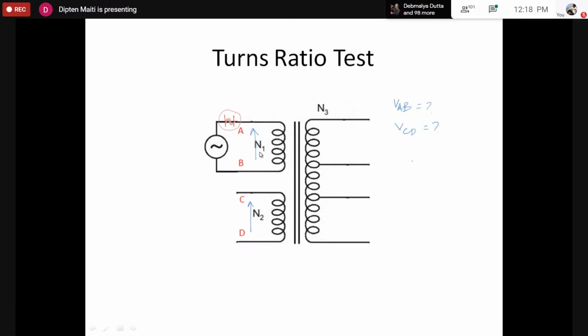If the fuse breaks, we have to try a few times, because it may happen that the magnetizing current is sometimes a bit higher, in which case the fuse may break. Otherwise, if you find your fuse breaks several times after repeated tests, that means this is not a transformer, or there is some fault with the transformer. However, if you find after a few attempts it works—usually it happens on the first attempt—otherwise we have to go for a few more attempts.